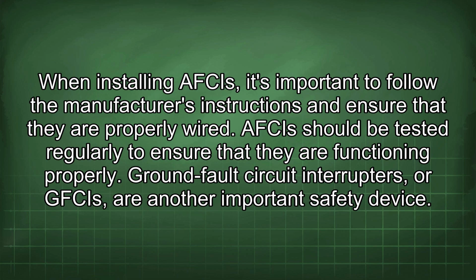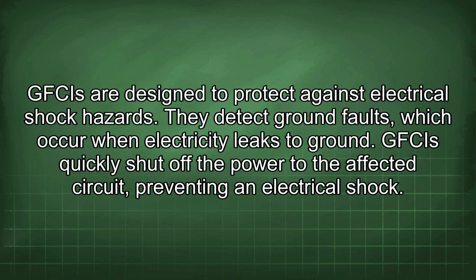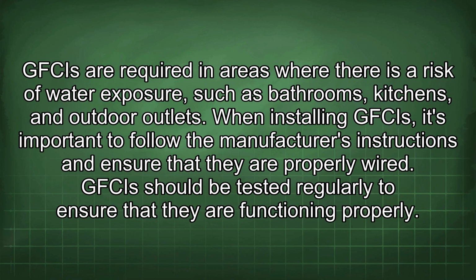Ground fault circuit interrupters, or GFCIs, are another important safety device. GFCIs are designed to protect against electrical shock hazards. They detect ground faults, which occur when electricity leaks to ground. GFCIs quickly shut off the power to the affected circuit, preventing an electrical shock. GFCIs are required in areas where there is a risk of water exposure, such as bathrooms, kitchens, and outdoor outlets. When installing GFCIs, it's important to follow the manufacturer's instructions and ensure that they are properly wired. GFCIs should be tested regularly to ensure that they are functioning properly.